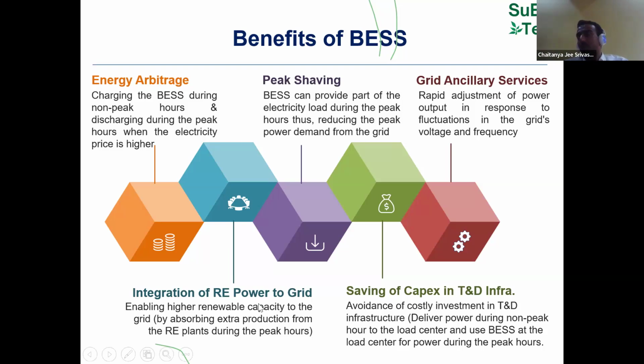Now, integration of renewable energy power to the grid. For example, even if on my roof I have capacity to install 10 kilowatt, my local BSES or my Bangalore electricity supply company, my local utility, will restrict me, saying they will only allow 5 kilowatt. Why is that limitation there? Because there is a limitation of the grid and distribution infrastructure - the local transformers, distribution transformers, might not have capacity to take power from additional unplanned new solar or wind being integrated to the grid. Accordingly, the grid needs to be strengthened.